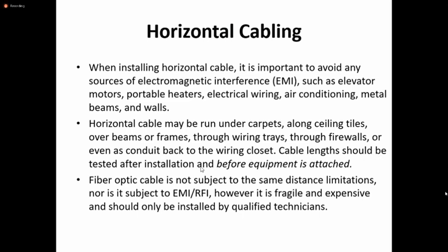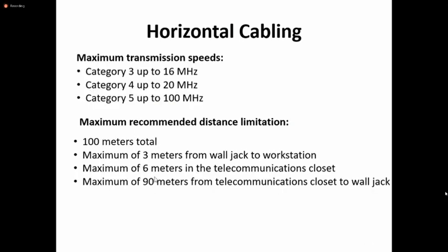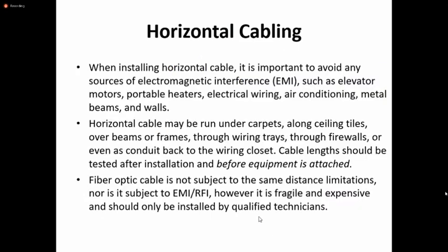Right. Cable length should be tested after installation and before equipment is attached. So you have to check the cable length. It should not exceed that amount, right? 100 meters. Actually the distance should be this, the limitations. So you have to check that before we actually connect your equipment, right?